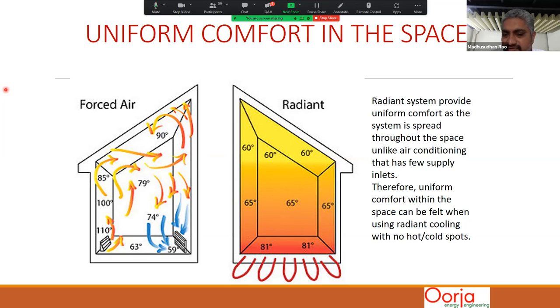But that is not there, because in radiant cooling the entire heat exchanger is spread over the space, and such hot, uncomfortable pockets are more or less eliminated. So you have better quality of cooling. One of the things that we don't appreciate here as much, but I've seen quite a bit of in Europe, is that the noise of the air delivery is actually a pollutant. Many people prefer not to have that noise. So in systems designed with radiant cooling, we can avoid such things.